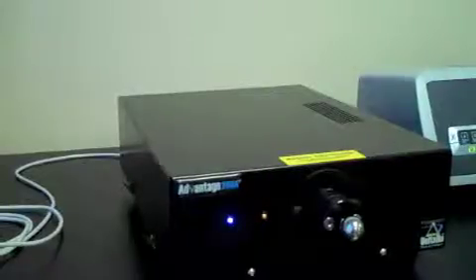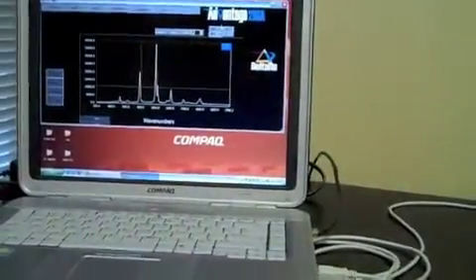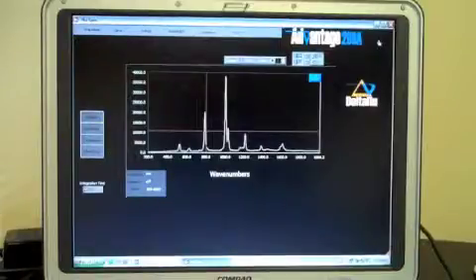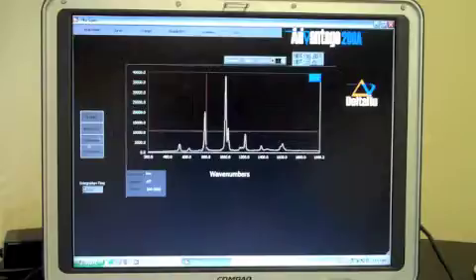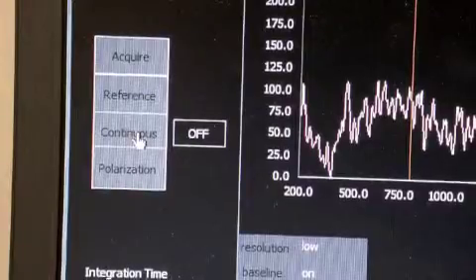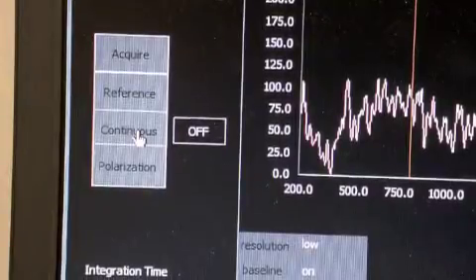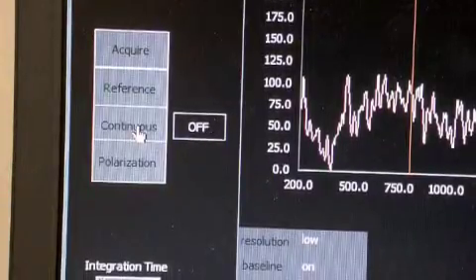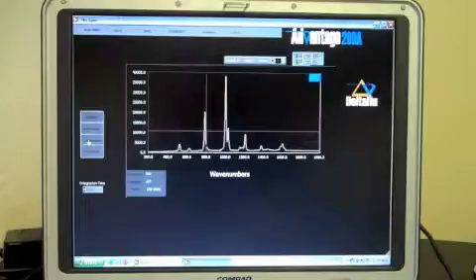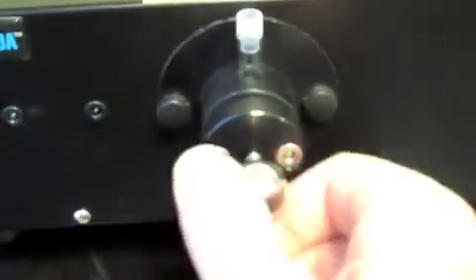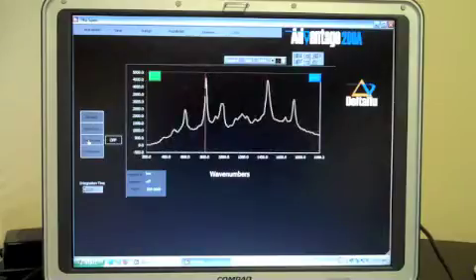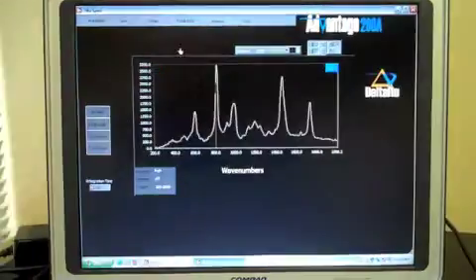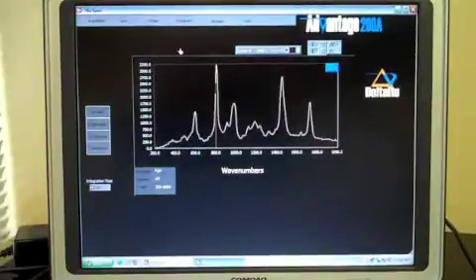Obtaining a good spectrum often requires adjustment of the position of the sample with respect to the laser beam. Record preliminary spectra by clicking on a button labeled continuous. You can optimize the peak size by rotating the round knob on the front of the black box. That will move the sample toward or away from the front of the spectrometer. By moving the position of the sample, you can optimize the signal.